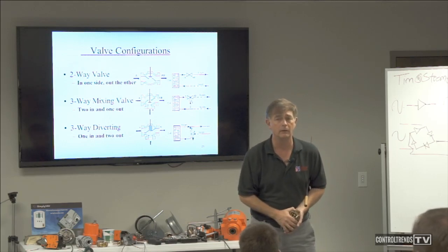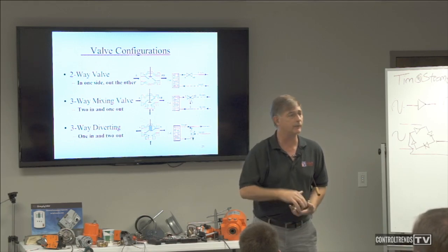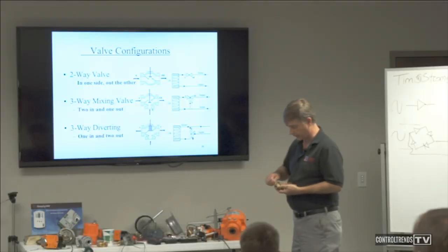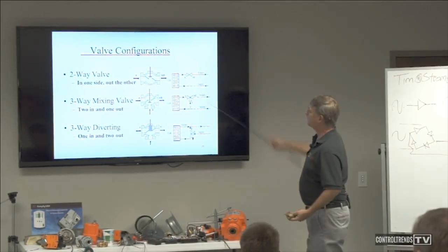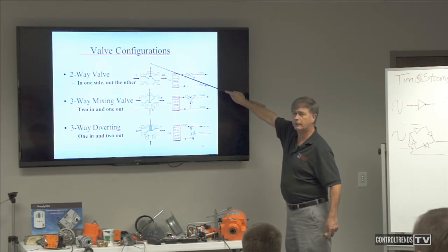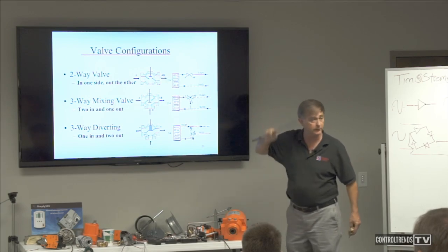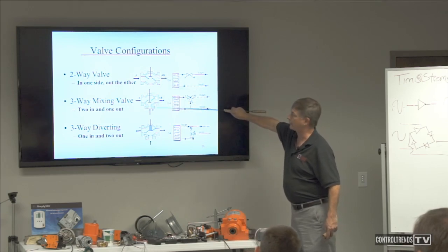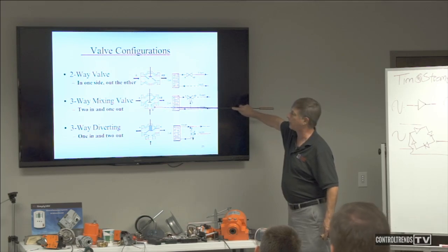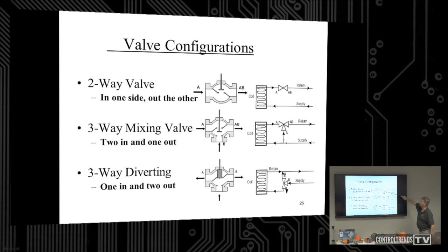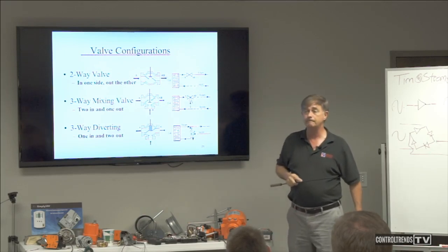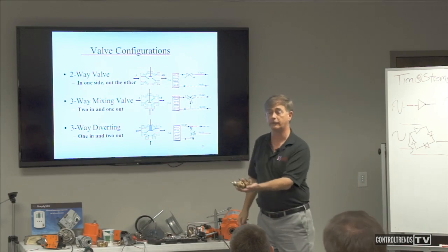How can you tell if you don't have numbers on the valve if it's normally open or normally closed? Notice, if an actuator pulls a stem up, it's going to pull it away from the seat. If this was normally closed, where would that stem be? It would look more like this. So, ignore this B port, this is just plugged off. Let's consider this is normally closed and this is normally open. With a stem up, do you see how stem up, this plunger goes against the seat here. Stem up, this goes away from the seat.